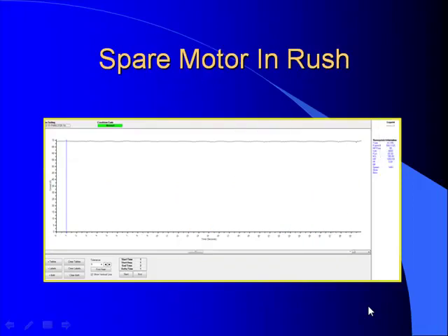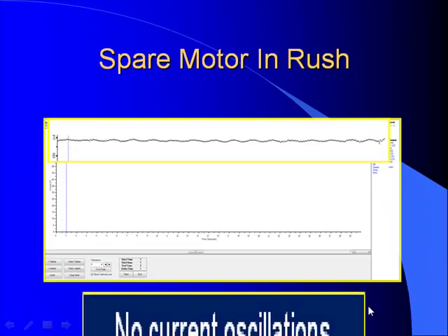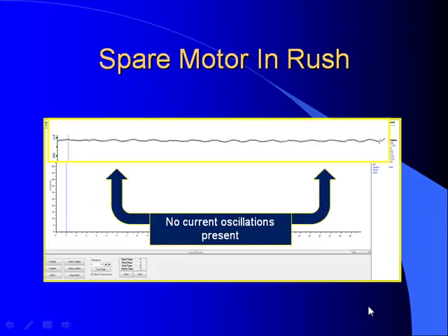Wow, what a difference. I mean, that is a much more stable signal. You can see it looks like the amperage is right around 70. So for the similar or same application, we have almost 10 amps less. Very little modulation in comparison, which really starts to point towards a possible rotating impedance variation. Now, that sounds real technical, but it basically starts to allow us to focus a little bit on the rotor as a possible influence to this changing current.